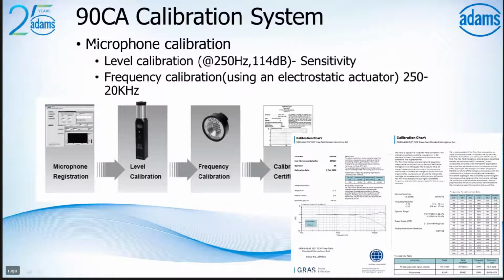So the 90CA, the microphone calibration system. I'm going to explain in a very simple manner, step by step, what the components are and how a calibration procedure is done using the 90CA. There are two steps. One is level calibration. As we have seen in the previous slides, we can use the pistonphone 42AP or 42AC for level calibration. We will be calibrating at 250 Hz, 114 dB, and getting the sensitivity of the microphone which you're going to use, say 50 millivolts per Pascal. So that finishes the first process, level calibration, and you get the sensitivity.